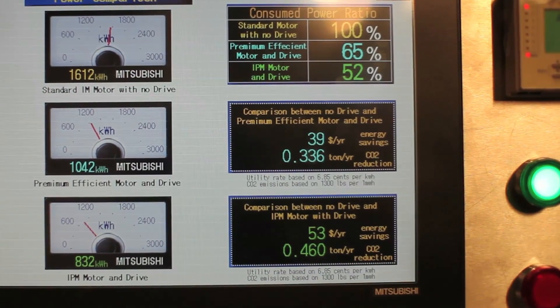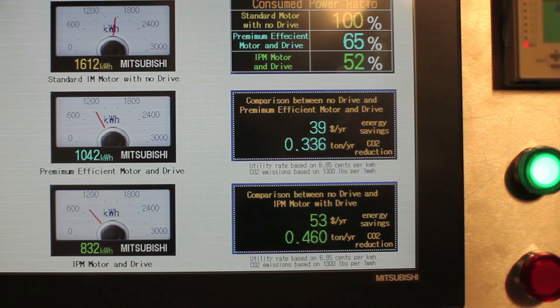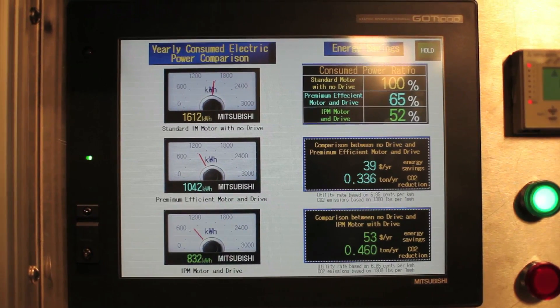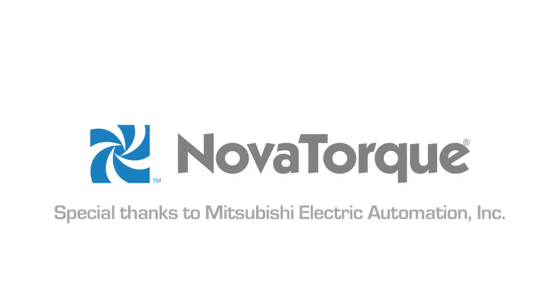The lower right quadrant of the screen shows the economical and environmental benefits of the higher efficiency motor systems. Assuming a utility rate of 6.85 cents per kilowatt hour, a VFD induction blower system can save $39 a year, while using a Premium Plus motor will reduce energy bills by $53 a year. The reduction in carbon dioxide emissions are also significant. Assuming emissions of 1,300 pounds of carbon dioxide per megawatt hour, using a VFD reduces emissions by nearly a third of a ton per year per motor, while the higher efficiency NovaTorque motor improves emissions reduction by a further 40%. We hope you enjoyed this performance demo featuring the NovaTorque higher efficiency Premium Plus motor with Mitsubishi's high performance variable frequency drives.